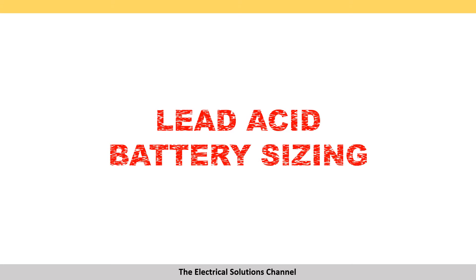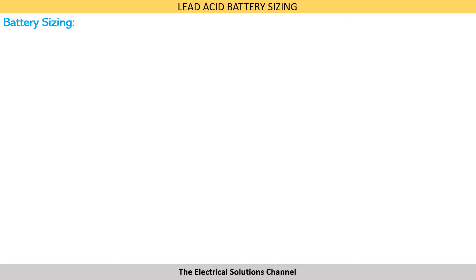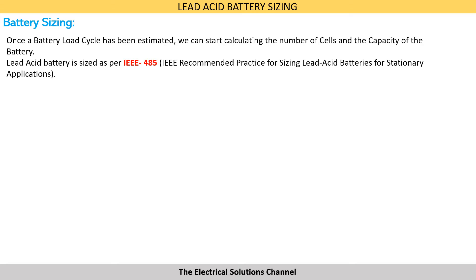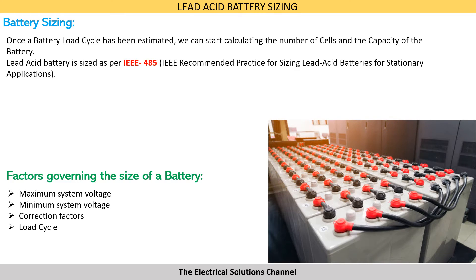Hey friends, welcome to my video on lead acid battery sizing. In my previous video I had explained how to estimate the battery load cycle - link to the video is given in the description. Once a battery load cycle has been estimated, we can start calculating the number of cells and the capacity of the battery. Lead acid battery is sized as per IEEE 485. The major factors governing the size of a battery are the maximum system voltage, the minimum system voltage, various correction factors, and most importantly, the battery load cycle.